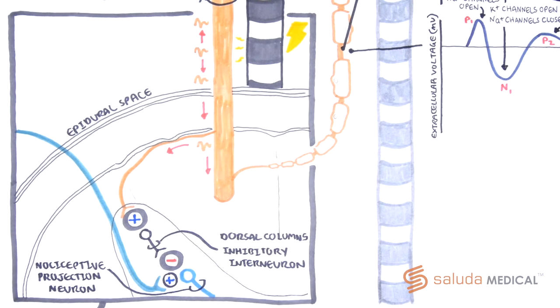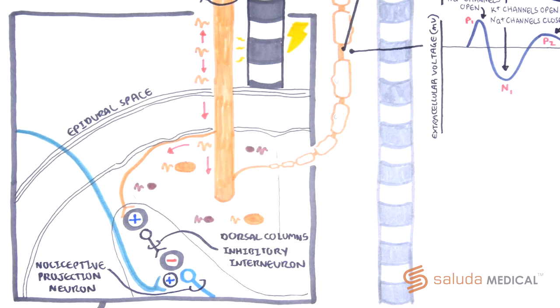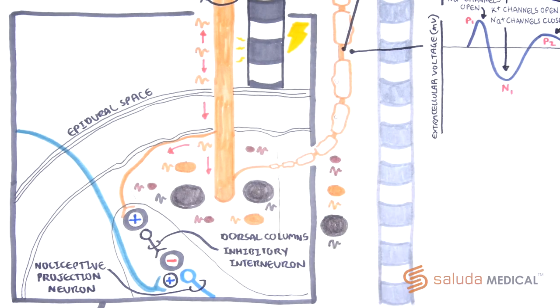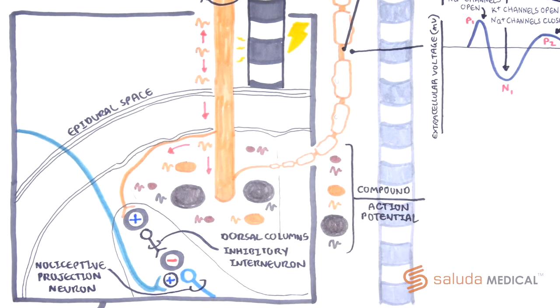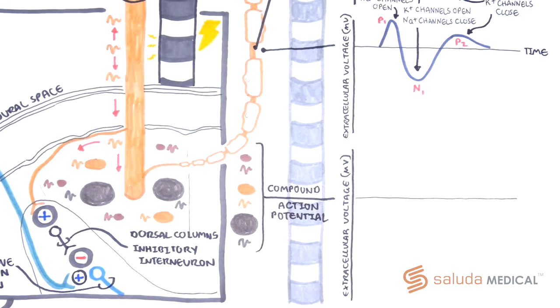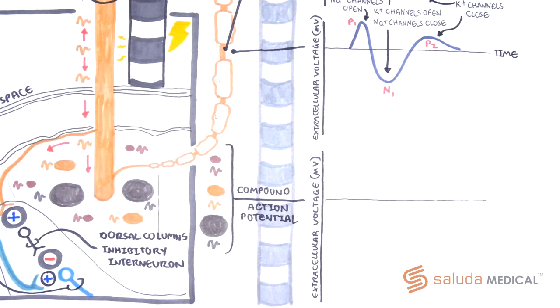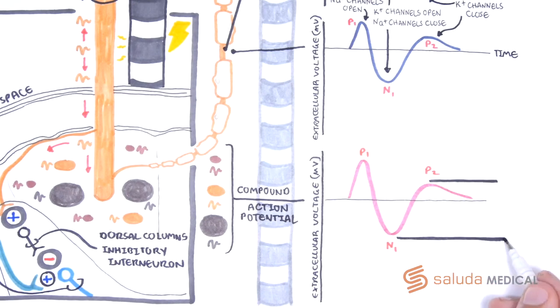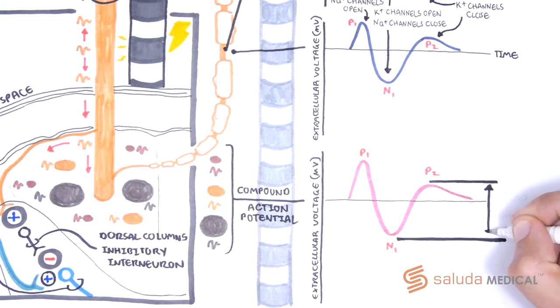In practice, however, spinal cord stimulation activates multiple fibers of different diameters, thereby triggering several action potentials from the dorsal column neurons, creating a compound action potential, the sum of all generated action potentials. As this compound action potential has been purposely elicited or evoked by some external source, it is called an evoked compound action potential, or ECAP for short. The size of the ECAP is typically calculated using the difference between the N1 and P2 peak.